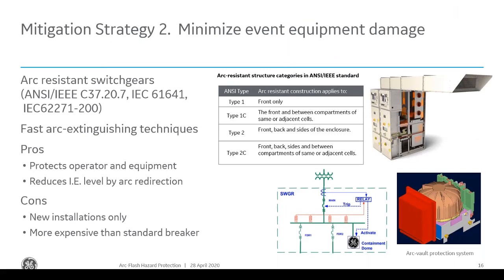Mitigation strategy number 2: we want to minimize equipment damage. When something does happen, we want to minimize the extent of the arc flash incident. One of the ways we do that is with arc resistant switchgear. There are various standards for these, for example the ANSI IEEE, and there are various types. These technologies to minimize equipment damage are the most effective strategies, but the con is they can be very costly. Arc resistant switchgear has been around for a while.